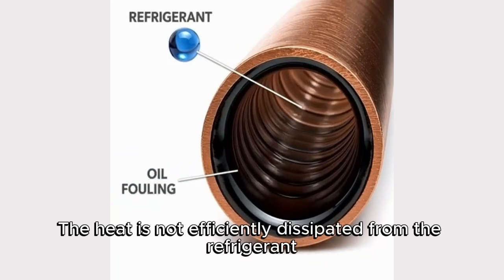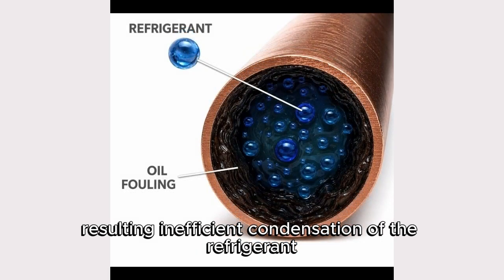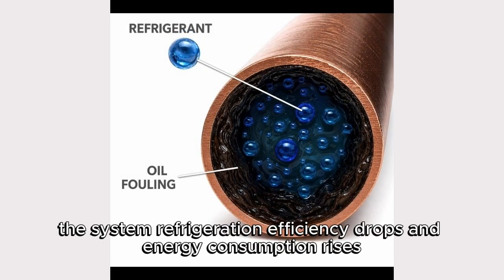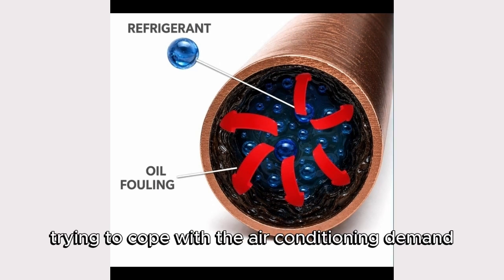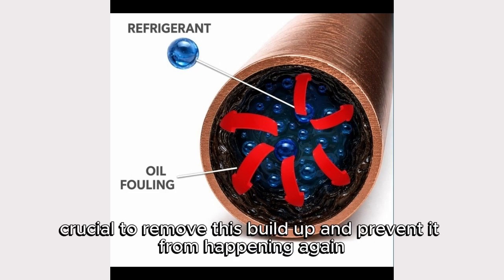The heat is not efficiently dissipated from the refrigerant, resulting in inefficient condensation of the refrigerant. Consequently, the system refrigeration efficiency drops and energy consumption rises, trying to cope with the air conditioning demand. It is thus crucial to remove this buildup and prevent it from happening again.